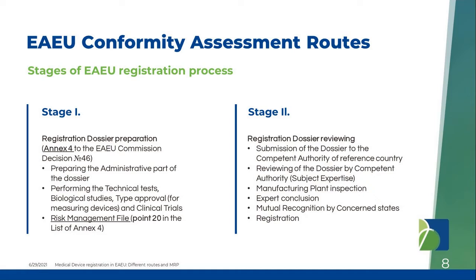And stage second, it's registration dossier reviewing. So it includes submission of the dossier, reviewing of the dossier, its subject expertise, manufacturing plant inspection, not for all medical devices, preparation of the expert conclusion, and after this stage, mutual recognition by concerned states, and it leads to registration.